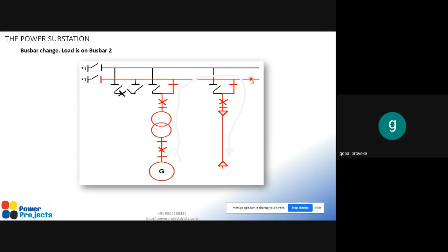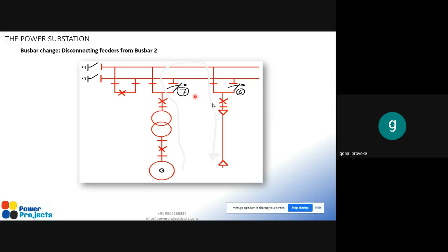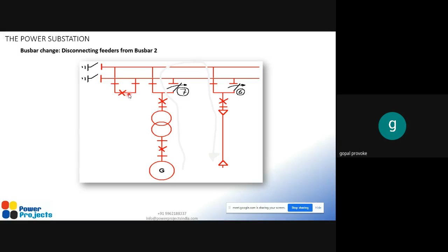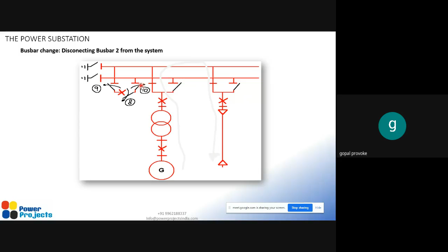Earlier only the bottom bus bar was energized. The top one was not energized. Now we are closing the isolator and energizing both. And now we are opening the isolator related to the bottom bus bar. The next sequence, we will be opening the breaker. So we will open the breaker in the 8th operation, and in the 9th operation we will open the isolator, and in the 10th operation we will open the other isolator.